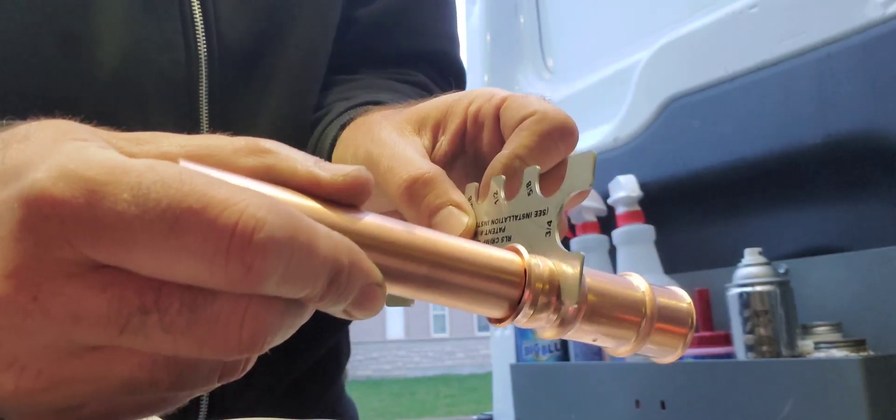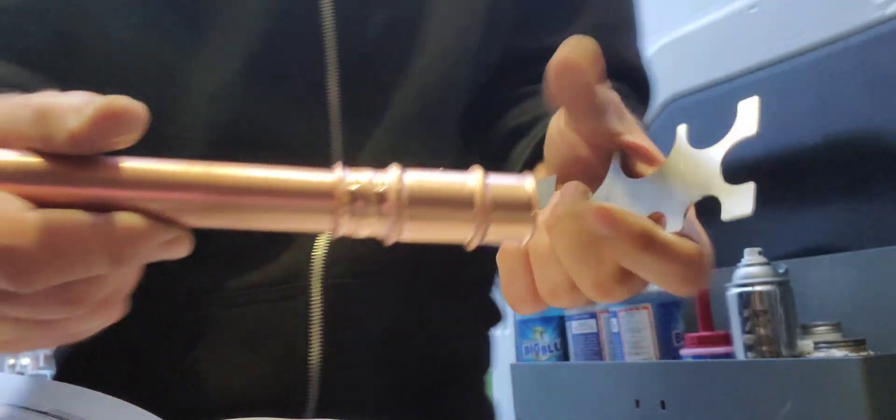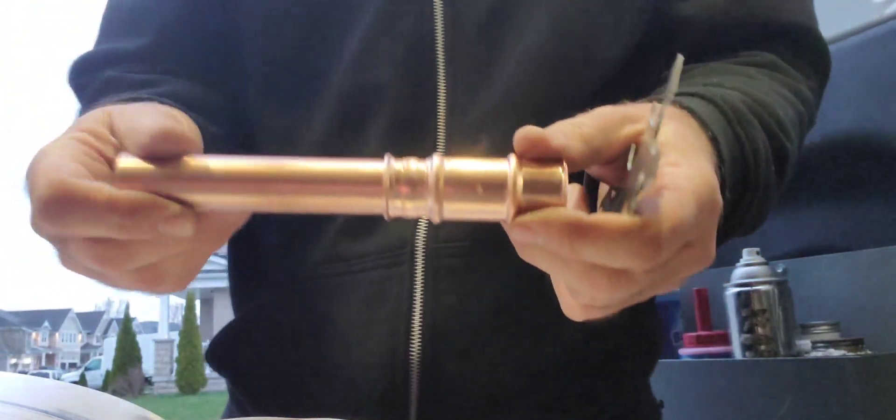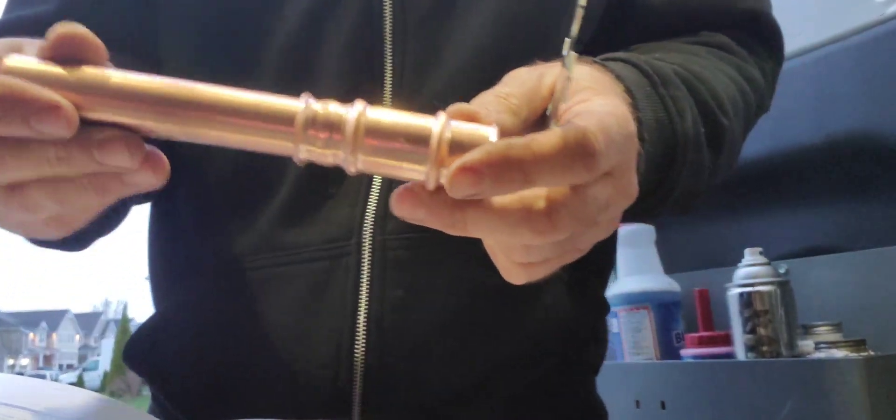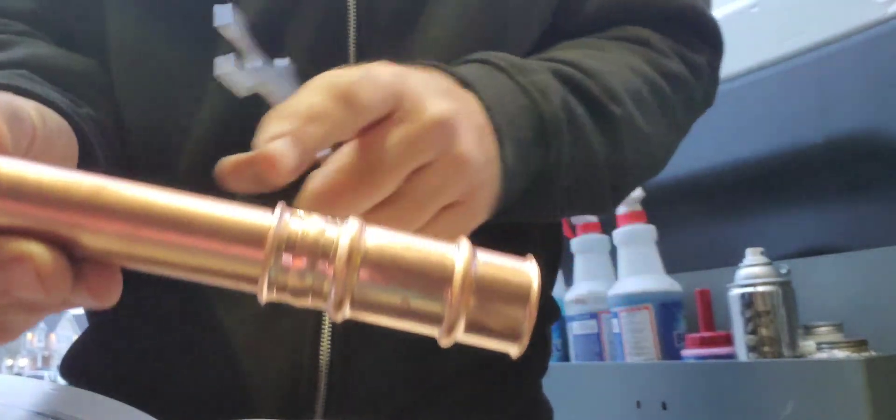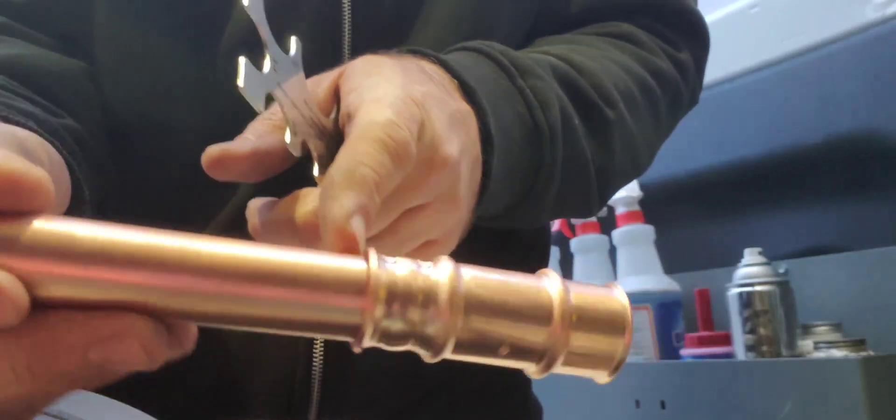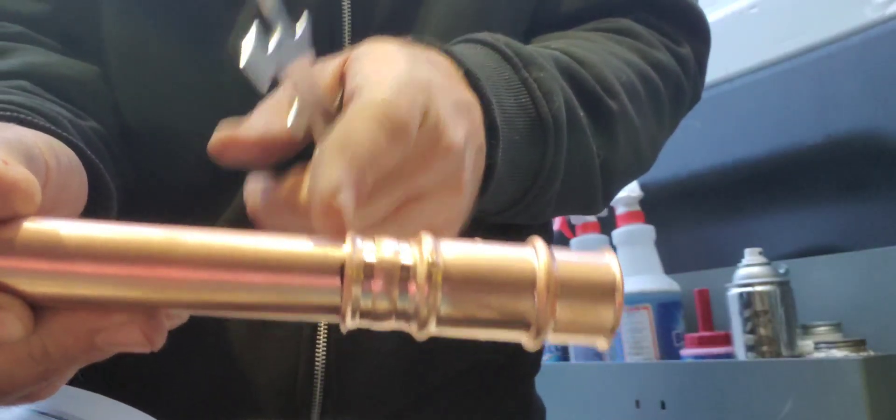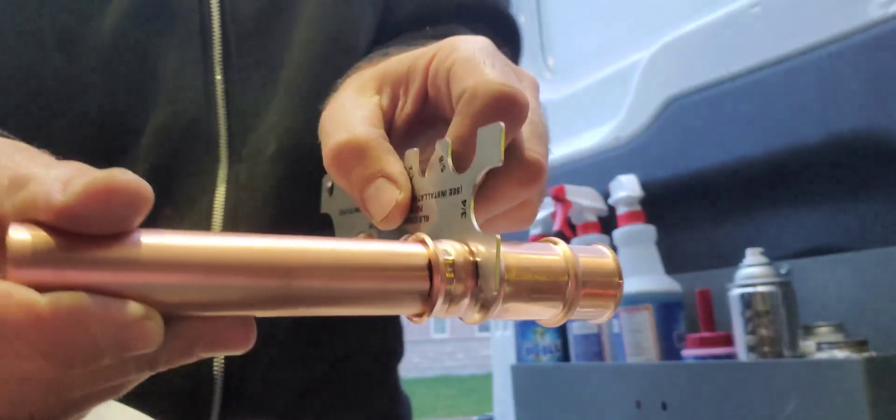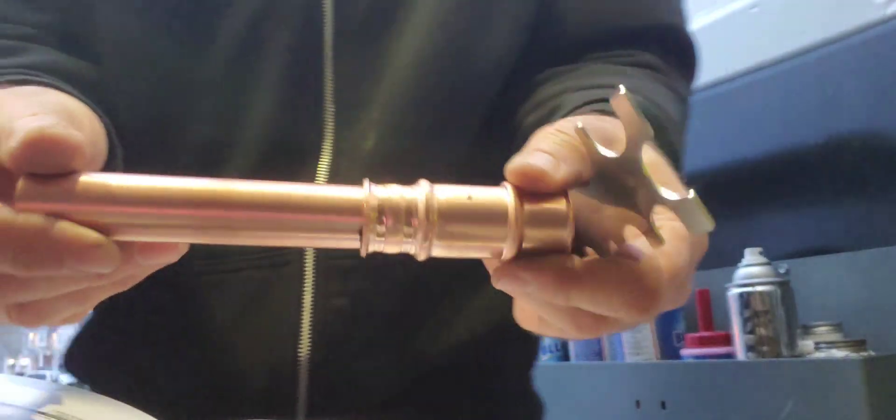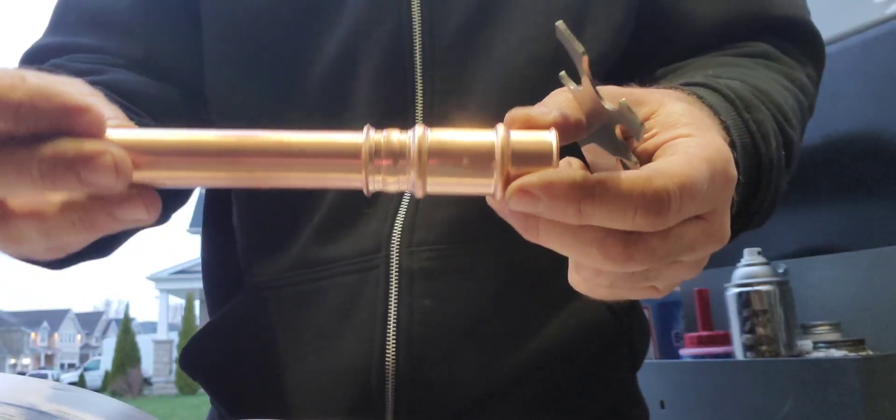That's it guys, very simple. There's skill involved in the cleaning and deburring, and you have to take notice of what you're doing with sizing up with the depth gauge, crimping with the tool properly, and then checking with the depth gauge afterwards. I'm pretty impressed with this tool so far. I can't wait to get it out onto a job site. Happy HVACing!